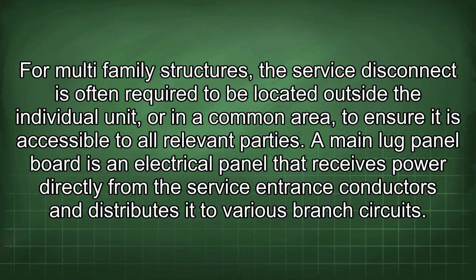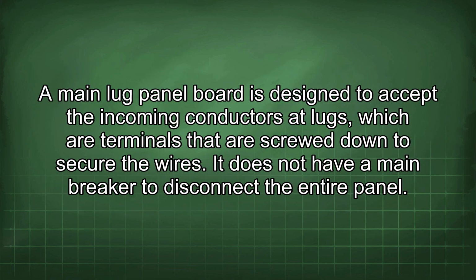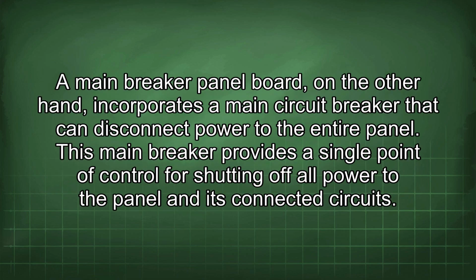A main lug panel board is an electrical panel that receives power directly from the service entrance conductors and distributes it to various branch circuits. A main lug panel board is designed to accept the incoming conductors at lugs, which are terminals that are screwed down to secure the wires. It does not have a main breaker to disconnect the entire panel. A main breaker panel board, on the other hand, incorporates a main circuit breaker that can disconnect power to the entire panel. This main breaker provides a single point of control for shutting off all power to the panel and its connected circuits.